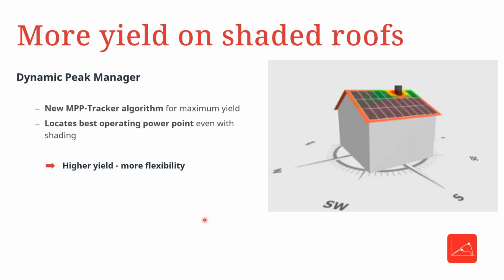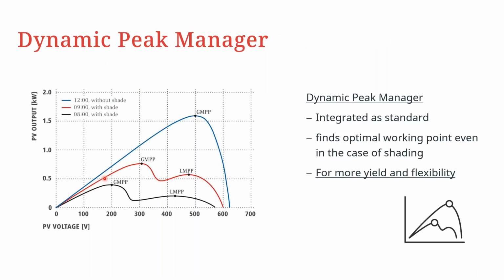Another cool feature about the Fronius Snap inverters, doesn't matter whether it's the Symo or the Eco Snap inverter, is the integration by standard of the Dynamic Peak Manager. This is another algorithm on top of the normal maximum power point tracking that enables the inverter to continue giving you maximum yield, even in the case of partial shading. So this therefore gives you higher flexibility and more yield in your system.